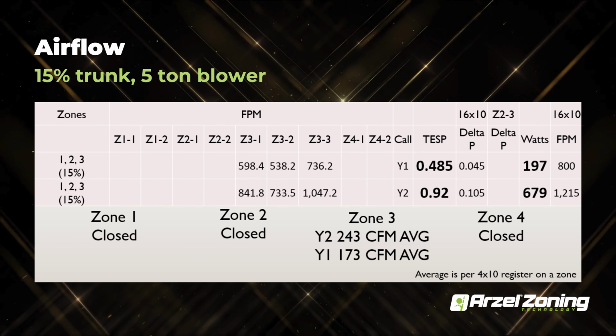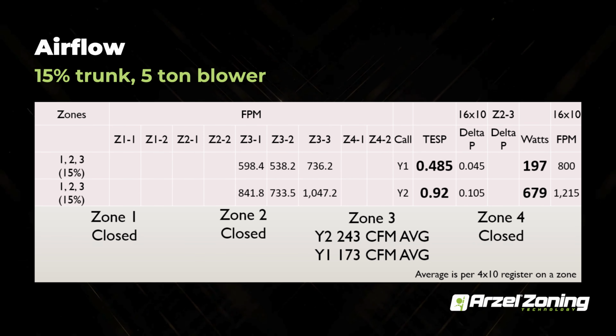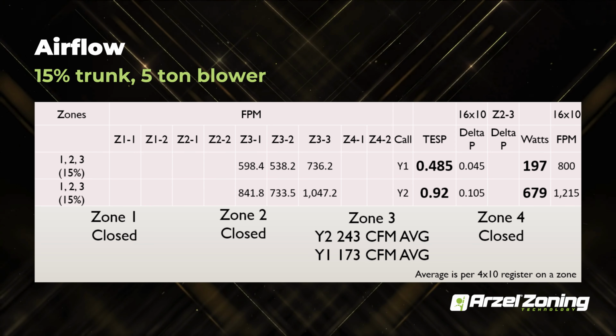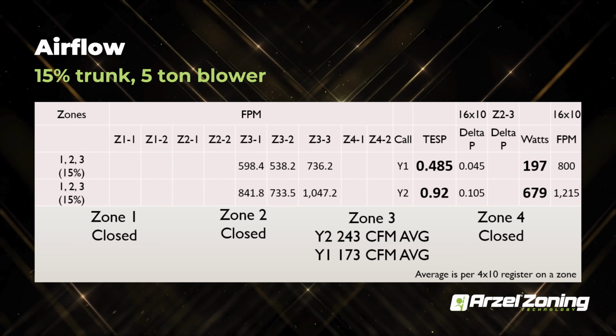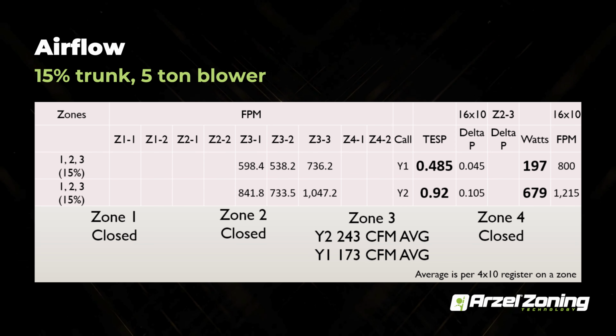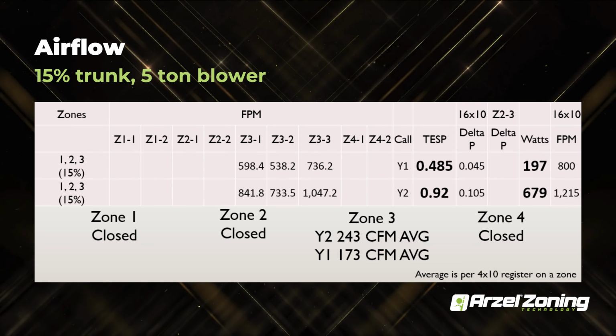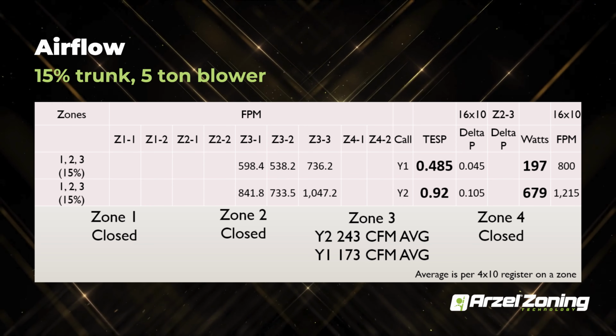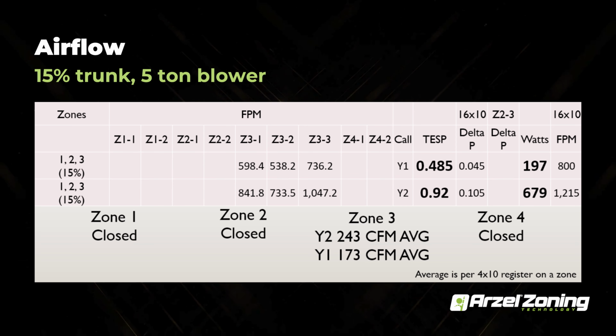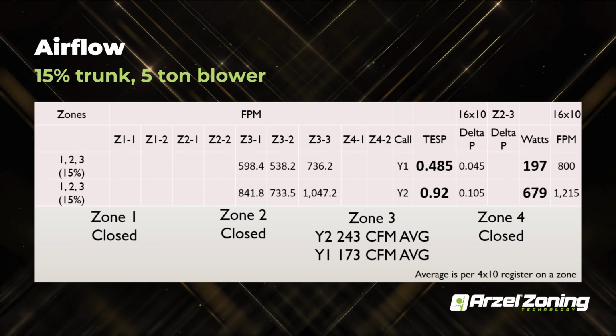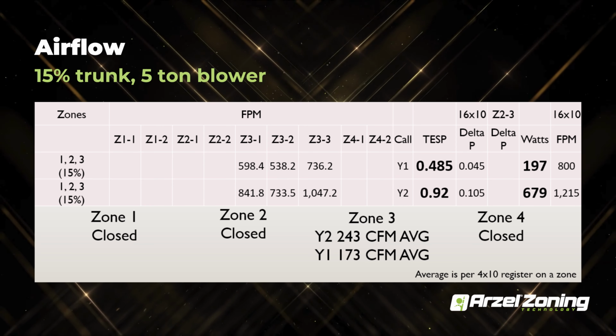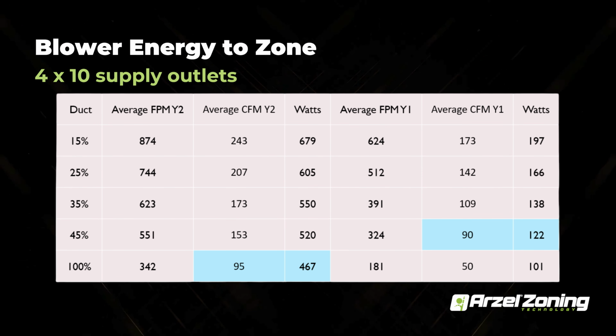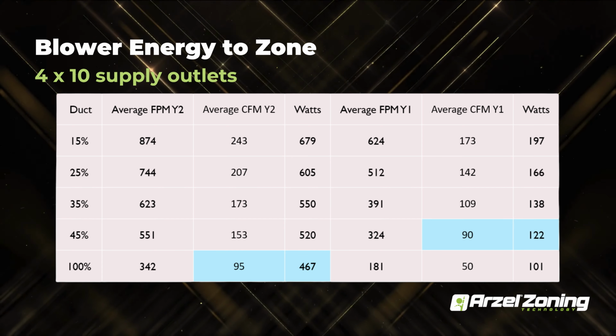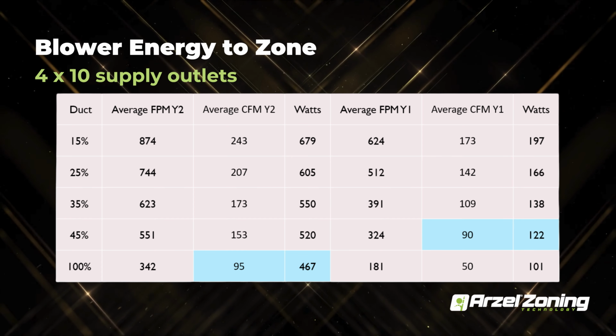And then our last example, which we would never really want to see a zone this small, but this is a 5-ton system. 15% of your trunk is actually open still. And you can see 0.485 is our total system static, 0.92 on a Y2 call. Then you've got 197 watts and 679 watts for your Y2 output. So what does this mean to you? This is kind of what you're looking at here.